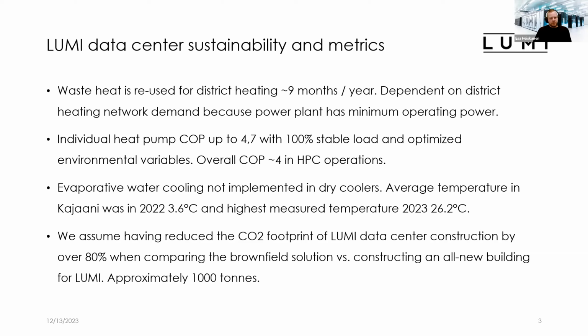Individual heat pump COP value is up to 4.7 with 100% load, which is stable and optimized. So all water flows and temperatures are optimized for the heat production. But overall COP, what we have been seeing so far, has been around 4 in the HPC operations from the Lumi.